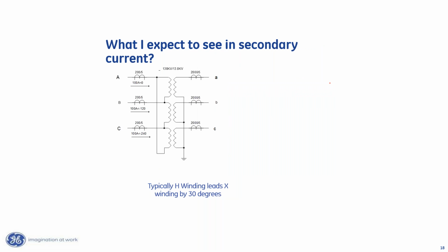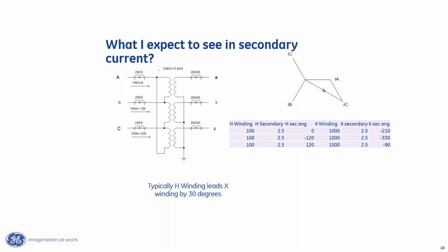Okay. What do I expect to see in secondary currents? This particular transformer is wonderful for secondary currents, right? Because look at these secondary currents. I don't have to worry about magnitude compensation on this particular transformer. That's why I say it's wonderful, because it's a 13.8 to 138 kV transformer. It means my magnitude compensation factor is 10. But look what I did. I did some trickery around my CTs. I made my high side CTs 200 to 5, and my low side CTs 2000 to 5. So I didn't have to do that magnitude compensation in my head.